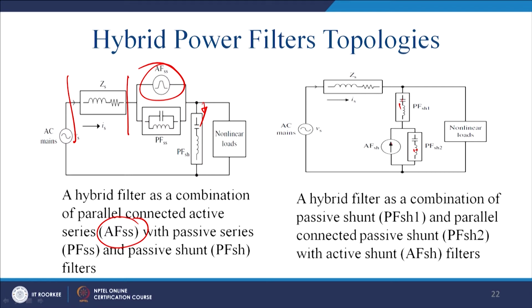With that you can have an active shunt filter. Mostly this solution is there when there is lower source inductance, and thus you do not have a greater value of the voltage, because you know, if there is a fifth harmonic voltage, even if you connect a resistive load, this will flow. So this fifth harmonic voltage arises due to the fifth harmonic current when it passes through the source harmonic, source inductance.